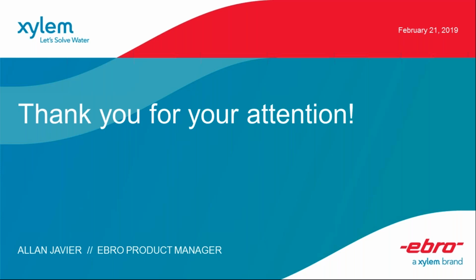Thank you, Michael. Can you hear me? Yes, you're fine. Okay. Calibration is an issue actually, and it's a very good question to start this discussion. Calibration is very important for the loggers that are especially used for validation purposes. I don't really recommend that you calibrate your loggers yourselves, especially during the annual required period. But considering that they're asking about data loggers without probes that they cannot immerse in an oil bath, then they can use a dry block. But what type of logger are they using? Exactly. Is that a validation logger or just a cold chain logger?